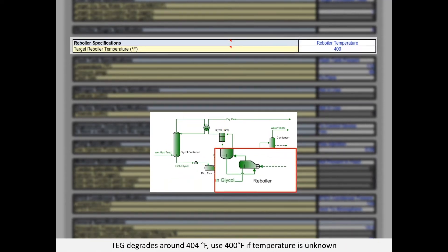By operating at close to atmospheric pressure and high temperatures, the glycol reboiler helps remove water and hydrocarbons to ensure a pure glycol is circulated back to the absorber. Common temperatures range from 360 to 400 degrees Fahrenheit. TEG begins to degrade above 400 degrees Fahrenheit, so it is not recommended to input reboiler temperatures greater than this value. If reboiler temperature is not known for the facility, we recommend using 400°F for a conservative estimate.